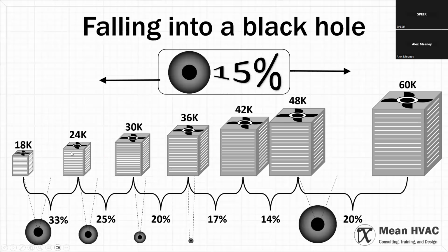So you must have enough latent capacity. Extra latent is not a bad thing, there's no actual limit on latent. There's some language in the manual that says there is, but the very next sentence says there isn't, so it's a confusing part of the book. Speaking in terms of physics, there's really no such thing as too much latent.